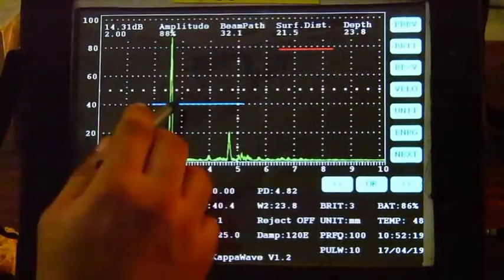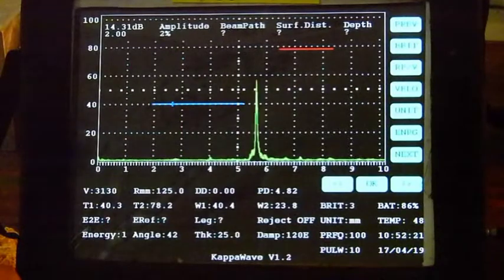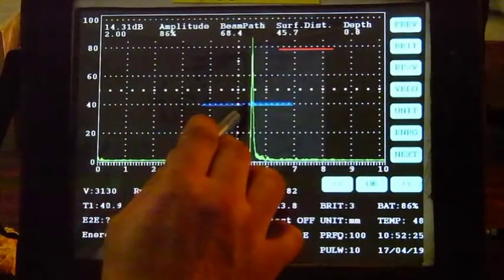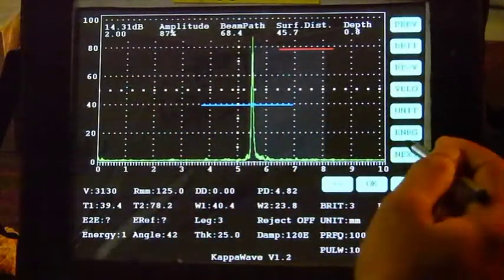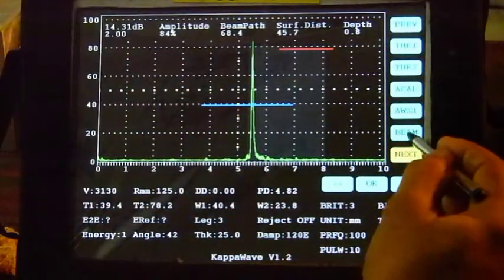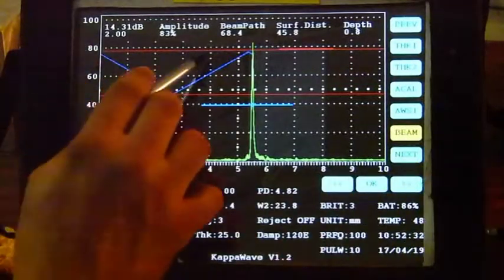These differences can be seen. This instrument has another feature like if you enter the probe angle and the thickness of the material it would give you a beam plot.